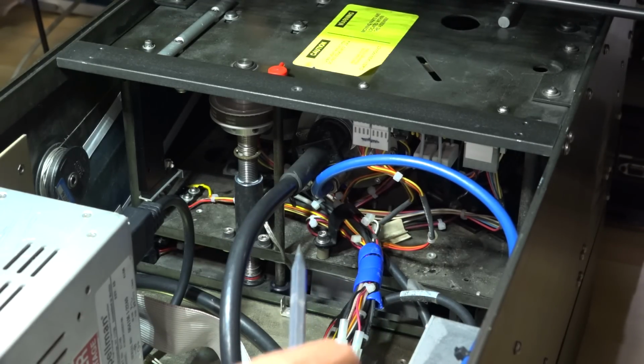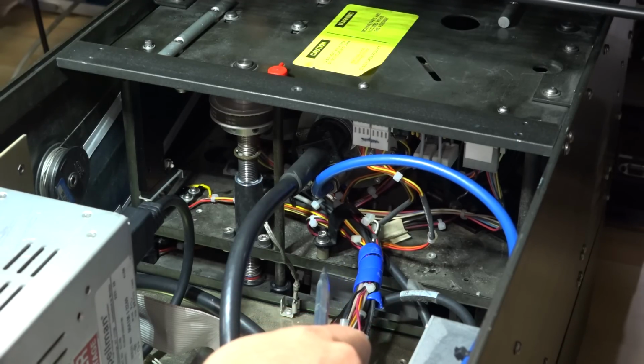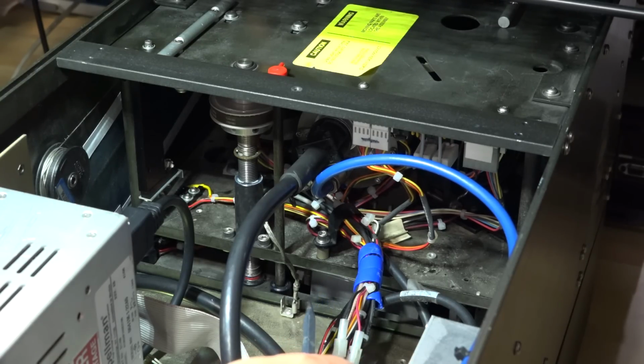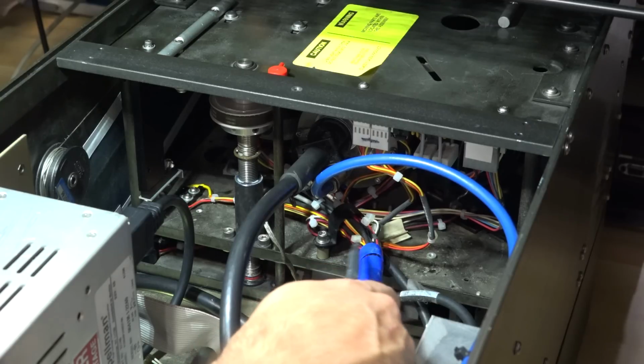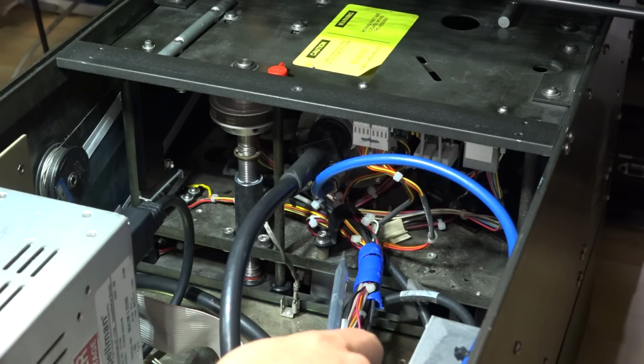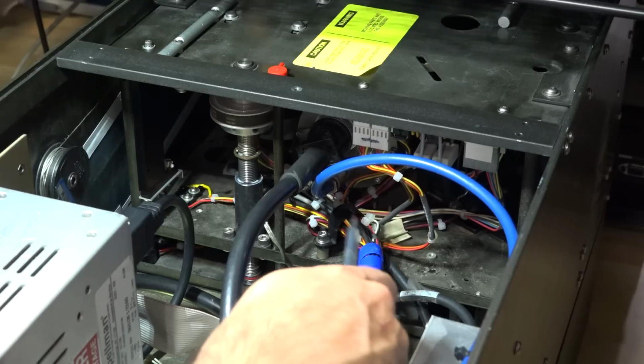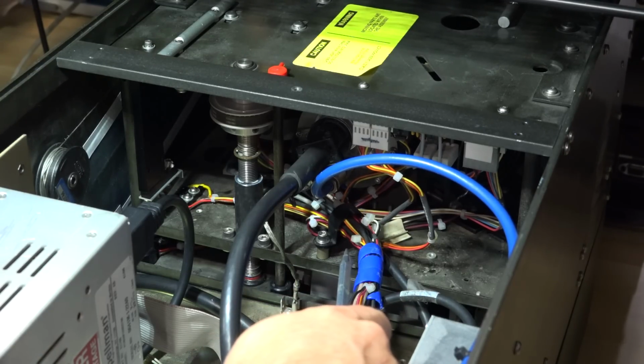Then the second issue I found out was that all those LEDs at the bottom that are supposed to illuminate the sample, a whole bunch of them were dead, and they were all white LEDs. So I had to replace all of those, which was quite annoying also, because they were all the way into really cramped spaces. And the third problem was that the camera was completely out of focus, so I had to finally adjust that. The issue is you can't test any of these until this whole thing is put back together.